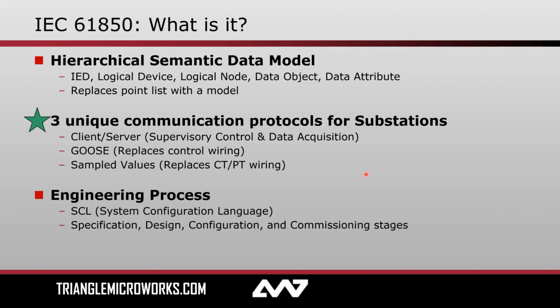So I always like to start by just doing that same overview. What is 61850? Well, it's not any one thing, and that's why we've broken it up into these multiple webinars. I already spoke about that hierarchical semantic data model, those containers within containers, which allow us to intelligently describe the data that are on our devices. Of course, the communication protocols, which is what will be our focus today: client-server, GOOSE, and sampled values. And then finally, the engineering process and the SCL that permeates all throughout it.